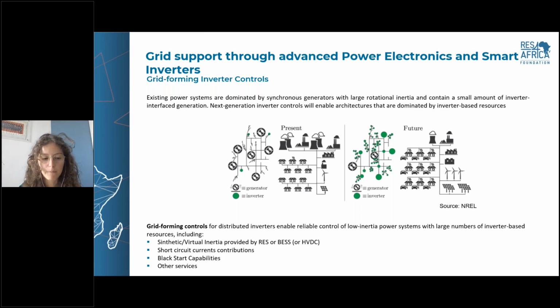This can also be called fast frequency control. These new grid-forming controls may also entail short circuit current contribution, so inverters that supply short circuit currents during faults, and inverters able to black start, so when there is no current in the system, they are able to start again. This is already implemented in inverters working in microgrids based on renewables, so it's something already available, but not yet widely diffused. It will be important for grid codes and regulation to require new units to supply these services through advanced controls.